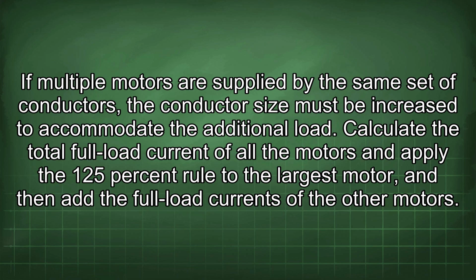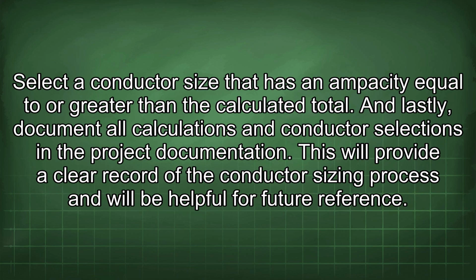Calculate the total full load current of all the motors and apply the 125% rule to the largest motor, and then add the full load currents of the other motors. Select conductor size that has an ampacity equal to or greater than the calculated total. And lastly, document all calculations and conductor selections in the project documentation. This will provide a clear record of the conductor sizing process and will be helpful for future reference.